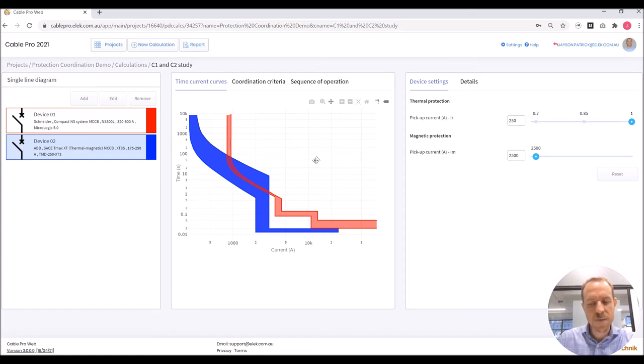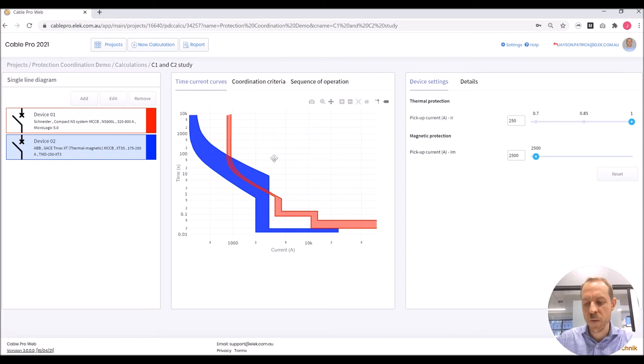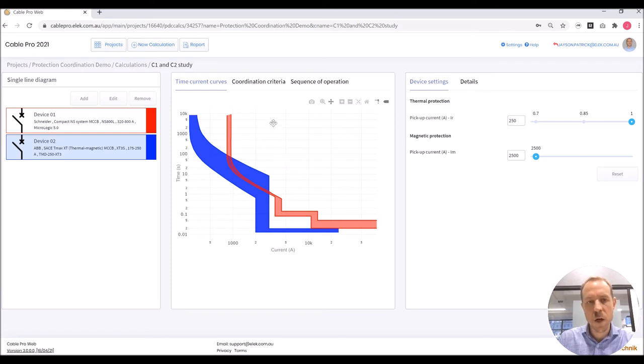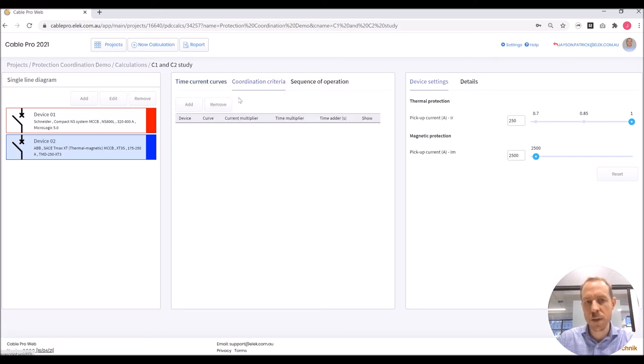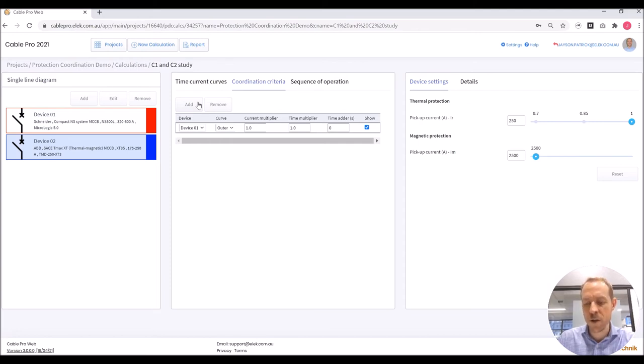We can see from the plots that there is significant overlap. To achieve coordination, enough separation must exist and must be maintained between the time current curves. I'm going to use the coordination criteria tools to help us. We had a requirement of a factor of 1.5 from the table in the standard, and I'm going to show this as an imaginary curve on the plot.